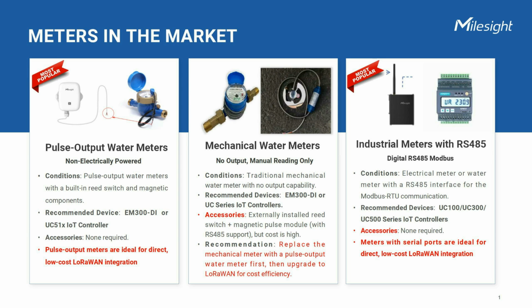And sometimes you may have traditional mechanical water meters. These old-school meters don't have any digital output at all. You're stuck reading numbers manually. Technically, you could add a pricey external module with a reed switch and magnetic pulse, and connect it to a UC controller. But honestly, it's cheaper to replace the meter first with a pulse output version, then upgrade to LoRaWAN. Save cash, skip the headache.